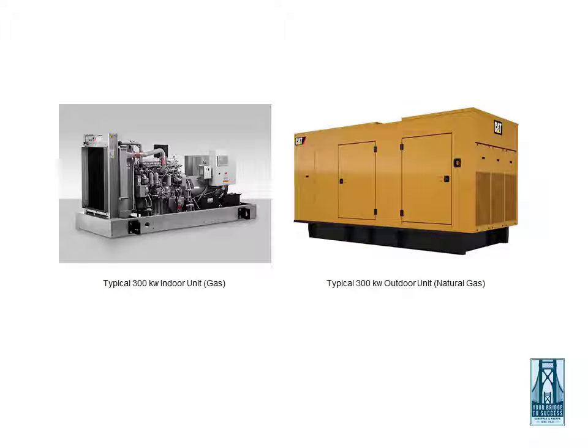In taking the building design's original design with natural gas, the load was 400 kW. If 60% of the loads are required to be backed up by an emergency generator, our backed up load would be 240 kW. But without calculating inrush current and starting across the line, we would potentially have a 300 kW natural gas unit. A typical 300 kW natural gas unit is feasible to be placed into a building or on site.